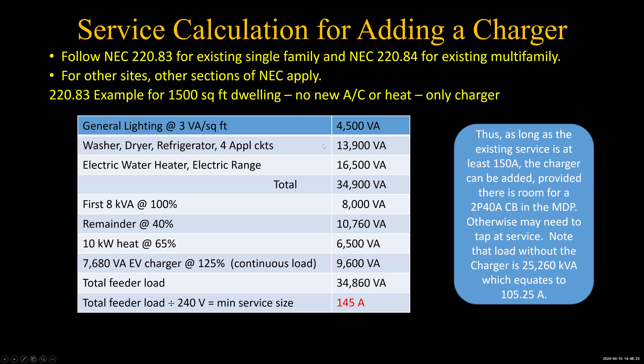Otherwise, you may have to do a line side tap or some other way to get it in there. Or if your panel is way too small and way too old, you might want to switch it out for a 42 position panel and have room for 2 EVs if you bump it up to 200 amps or something. Or if you don't bump it up to 200 amps, depending on how your chargers communicate. So anyway, here is your calculation, pretty straightforward. And we thought we'd put a little bit of meat into this, otherwise it's conjecture, predicting what's going on.